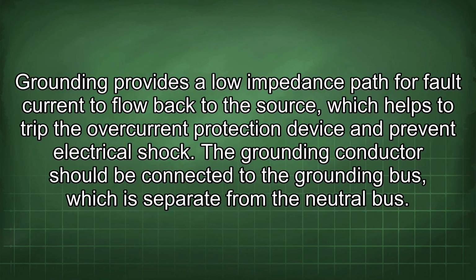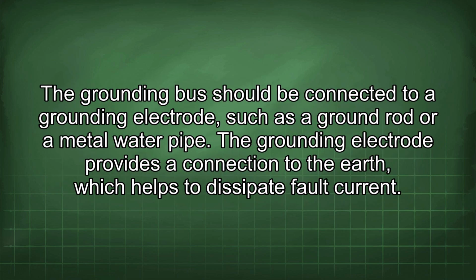Grounding provides a low impedance path for fault current to flow back to the source, which helps to trip the overcurrent protection device and prevent electrical shock. The grounding conductor should be connected to the grounding bus, which is separate from the neutral bus. The grounding bus should be connected to a grounding electrode, such as a ground rod or a metal water pipe. The grounding electrode provides a connection to the earth, which helps to dissipate fault current.